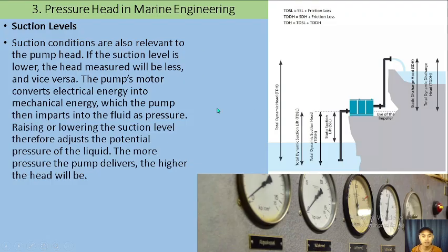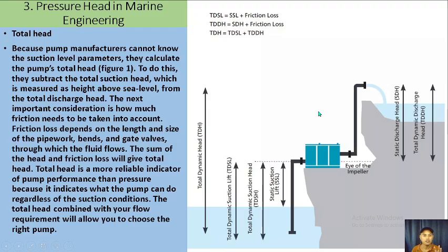And then we have also the discharge head on this part, on the discharge side of the pump. Usually the discharge head is positive because it always goes up. But you will have losses depending on the friction of the liquid, your pipe curves, or how big your pipe is. So there are restrictions or losses that might happen, and those will be negative. In computing your total head, you must add both the suction head and the discharge head, including all the losses.